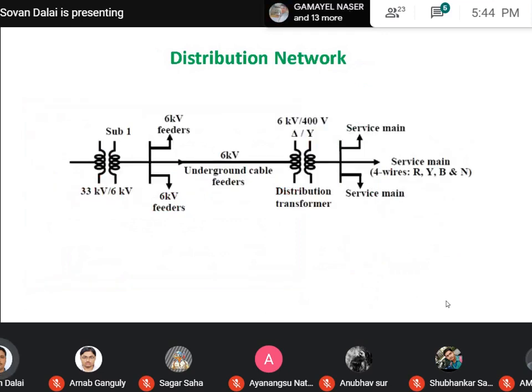And this is the typical representation of the distribution network. Say suppose there is a distribution network transformer, 33 kV by 6 kV, and that will be fed to the 6 kV feeder. The feeder is basically connected to the bulk consumer. And here, instead of a transmission line, the power is flowing through underground cable. In Kolkata and surrounding urban areas, the power is transmitted through underground cable, and that is basically sent to the distribution transformer.